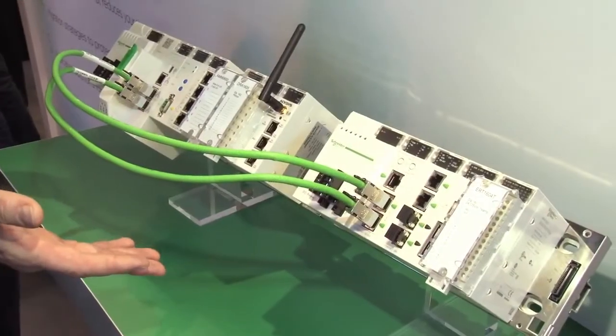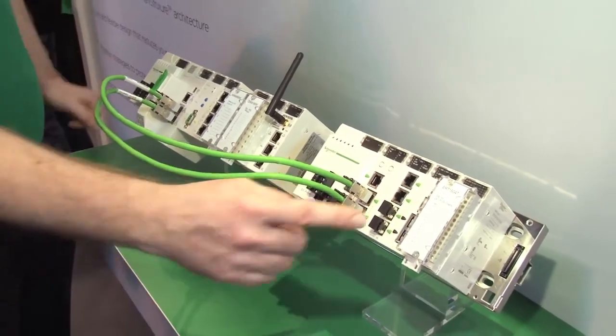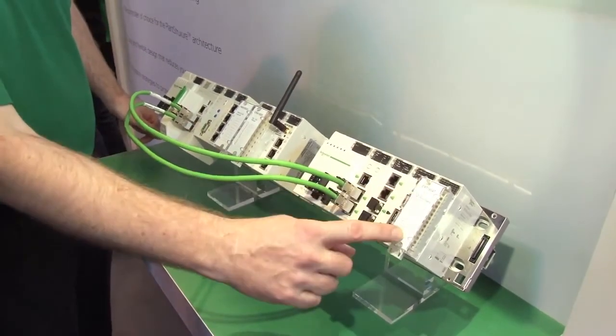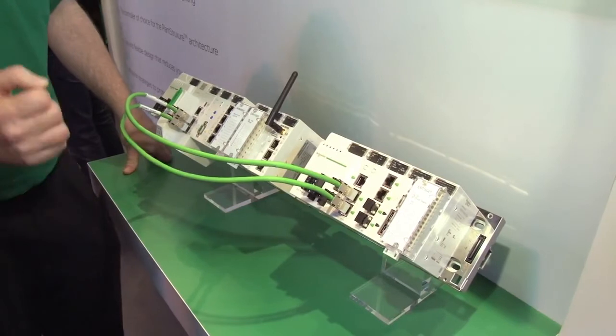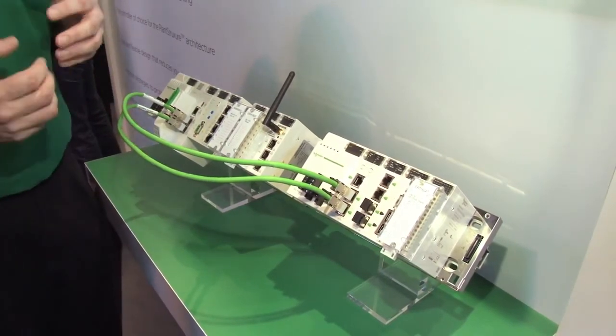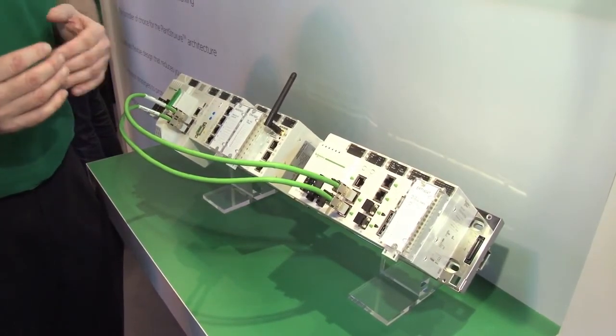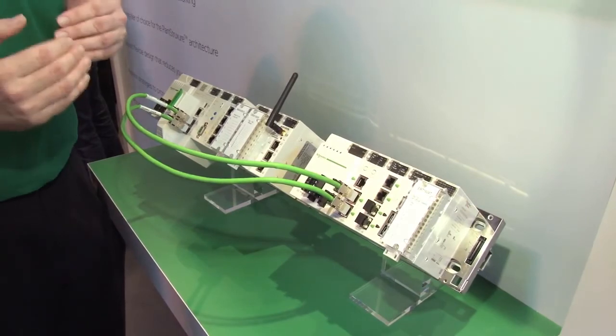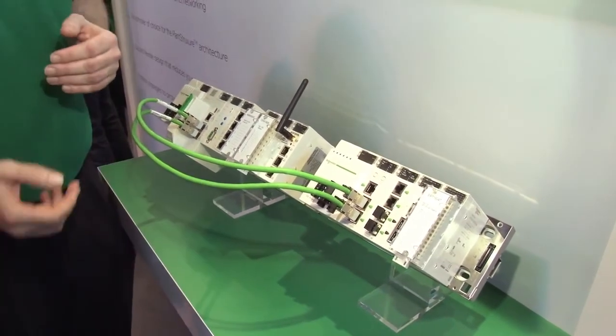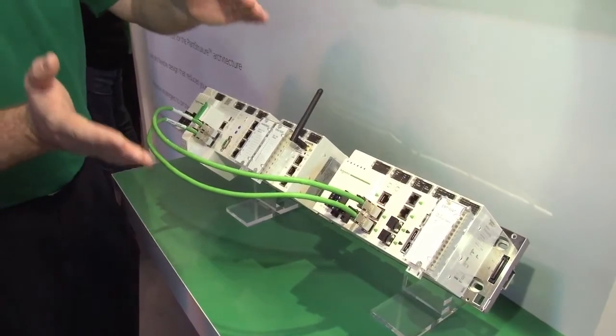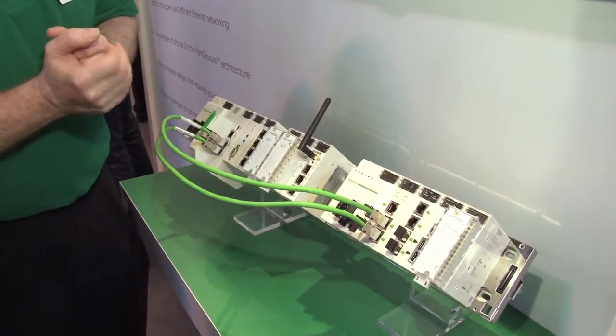Other elements of the M580 are on show here. We have this dedicated module here, the ERT module, that's capable of time stamping. So in terms of capturing sequence of events data to track and trace the root cause of a failure, this module can timestamp and hold all that data on board down to a resolution of 10 milliseconds.